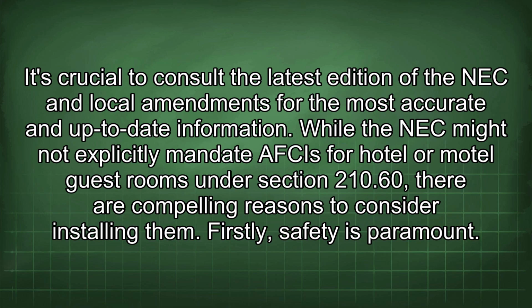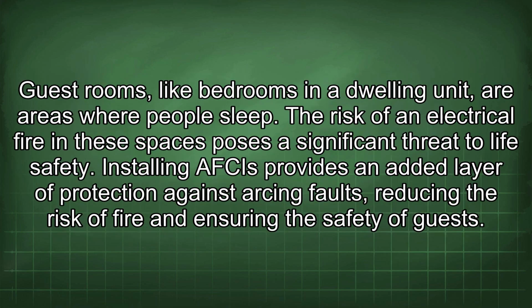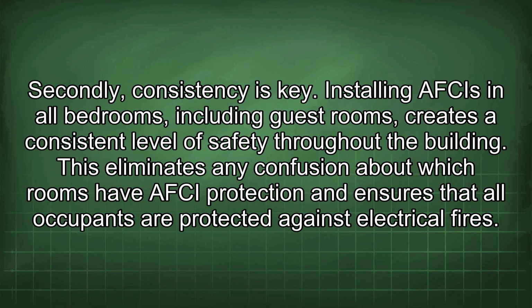While the NEC might not explicitly mandate AFCIs for hotel or motel guest rooms under Section 210.60, there are compelling reasons to consider installing them. Firstly, safety is paramount. Guest rooms, like bedrooms in a dwelling unit, are areas where people sleep. The risk of an electrical fire in these spaces poses a significant threat to life safety. Installing AFCIs provides an added layer of protection against arcing faults, reducing the risk of fire and ensuring the safety of guests. Secondly, consistency is key. Installing AFCIs in all bedrooms, including guest rooms, creates a consistent level of safety throughout the building. This eliminates any confusion about which rooms have AFCI protection and ensures that all occupants are protected against electrical fires.